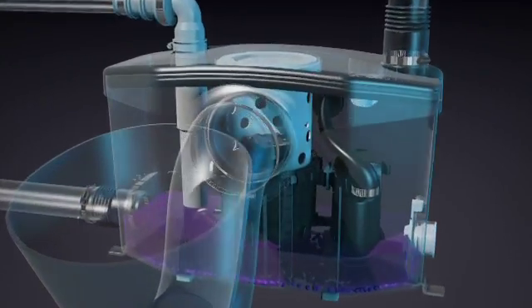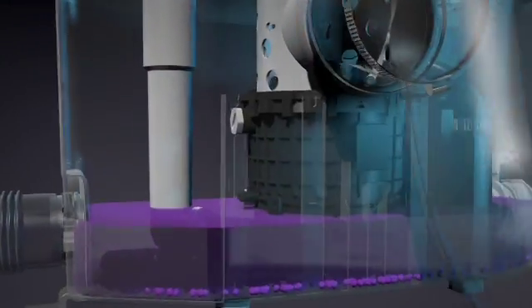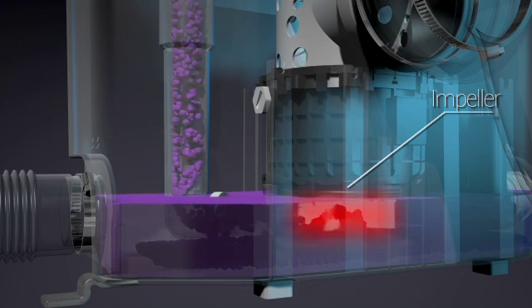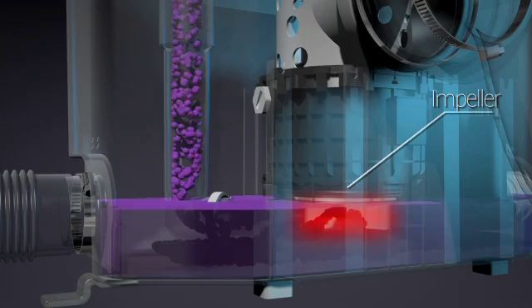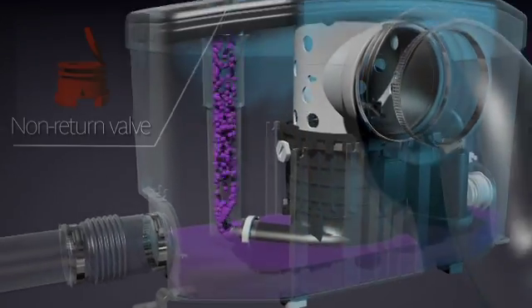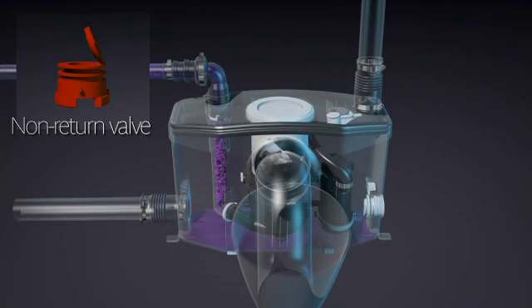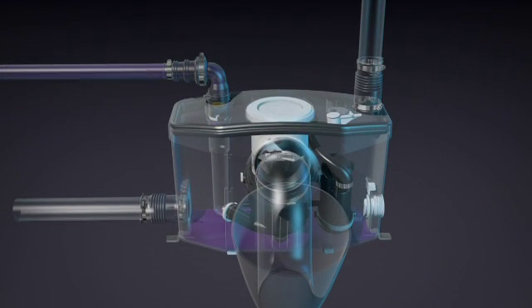These are then picked up by the impeller and pumped out through the internal discharge pipe. Once it exits the pump, the waste goes through a discharge elbow which connects to the 3-quarter inch pipe. A built-in non-return valve prevents the waste water from traveling back into the pump once the system turns off.